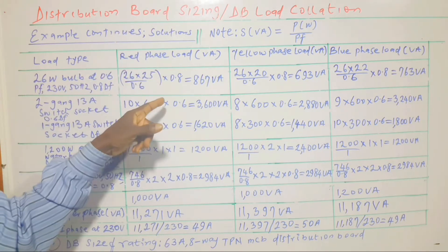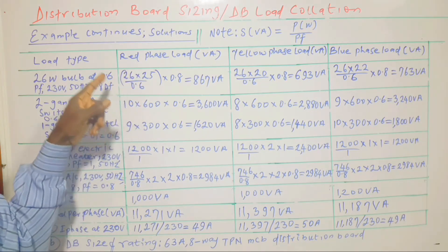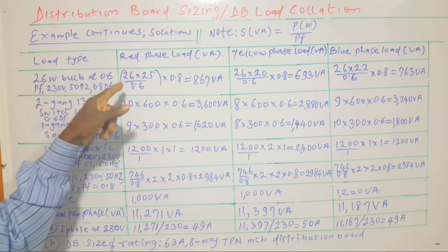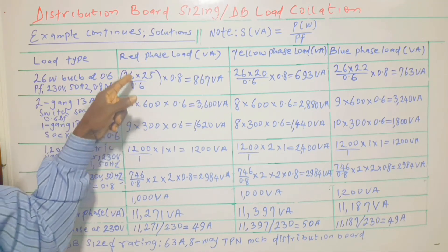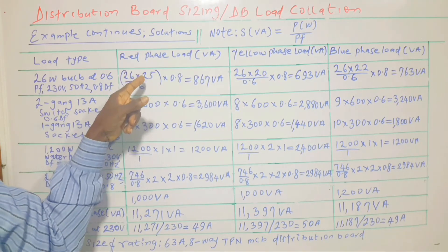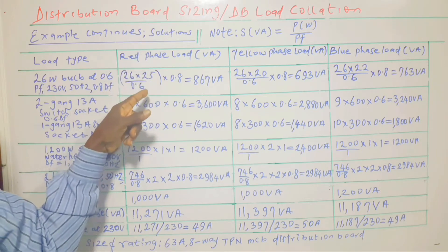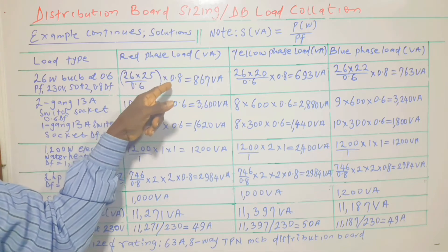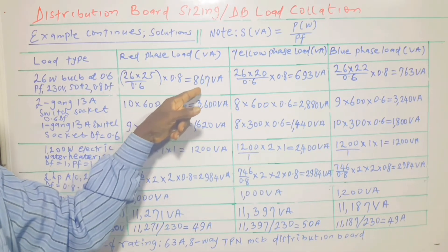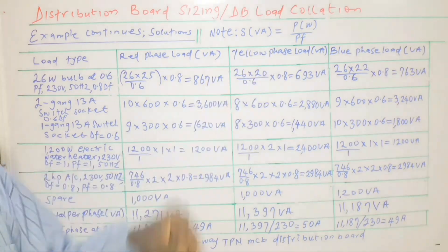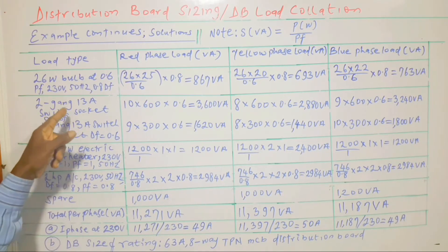On the red phase, we have 25 bulbs, each rated 26 watts. The important step is to convert 26 watts to VA by dividing by the power factor. That gives the VA rating, which is then multiplied by the number of bulbs on the red phase. We then multiply the result by 0.8, which is the diversity factor, to get the final value for the red phase bulbs.